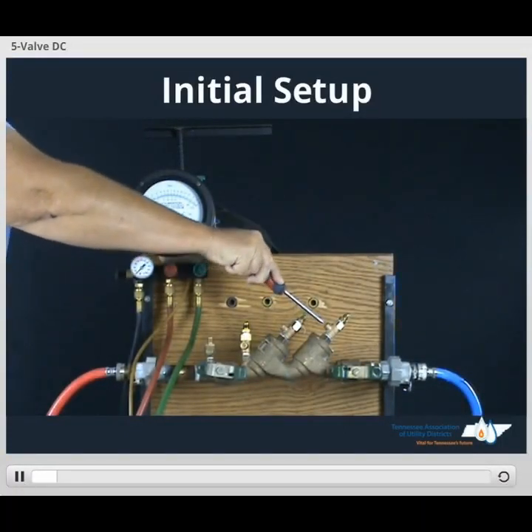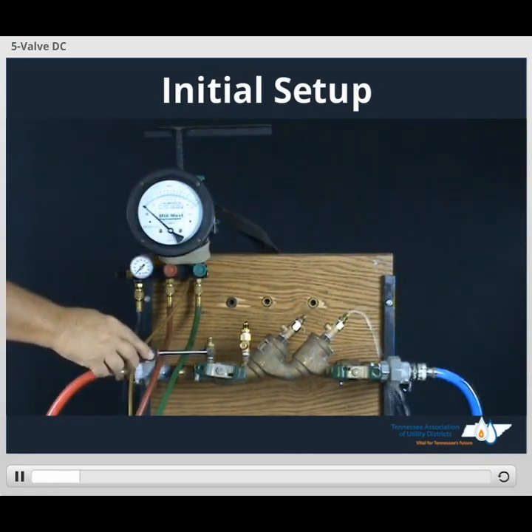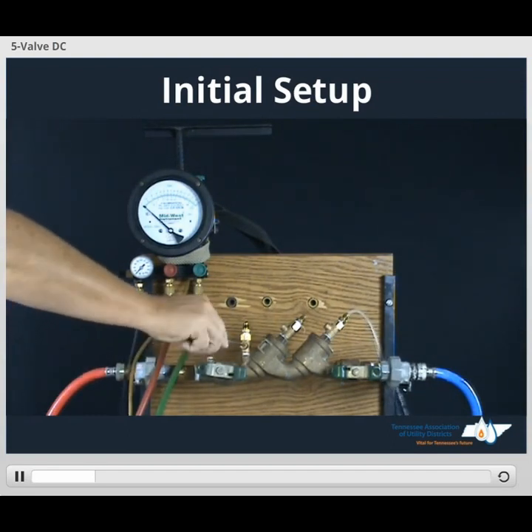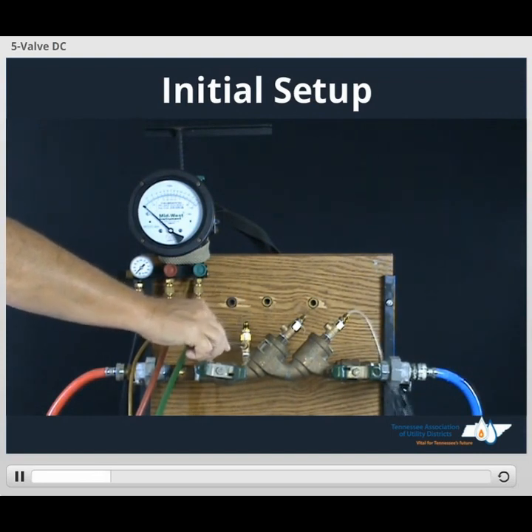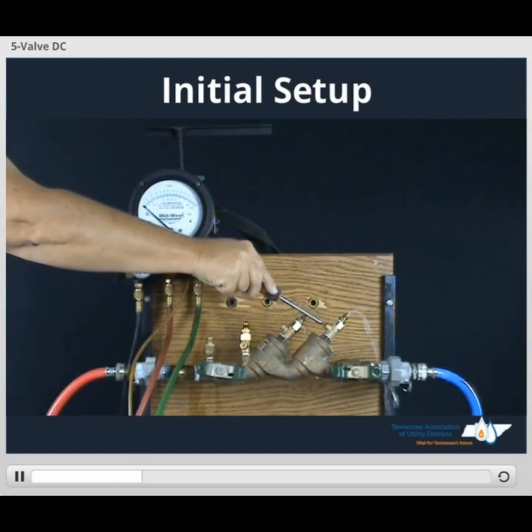Open test cock number 4, allow it to continue to run. We'll open and flush test cock number 1 if you plan on using it. We'll open test cock number 2, flush it, close it back. Open test cock number 3, flush it out, close test cock number 3. Then we'll close test cock number 4.